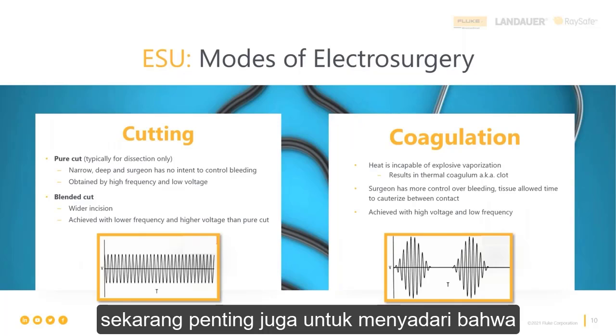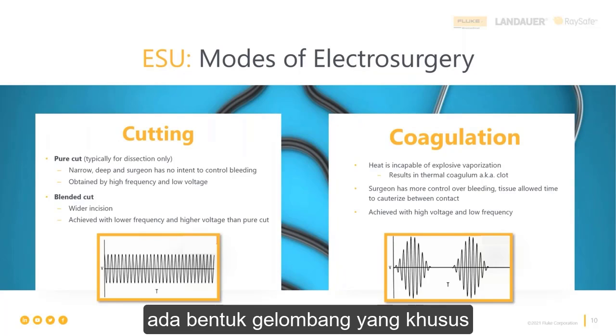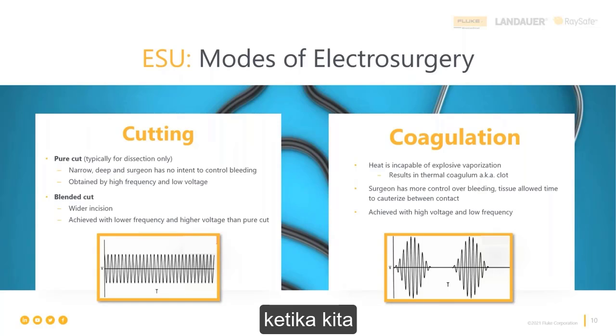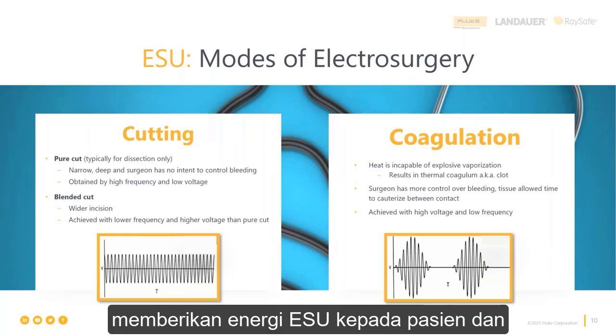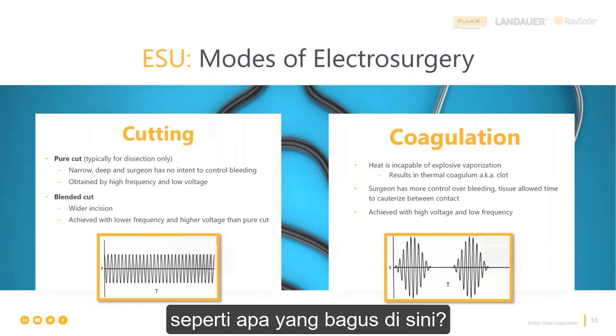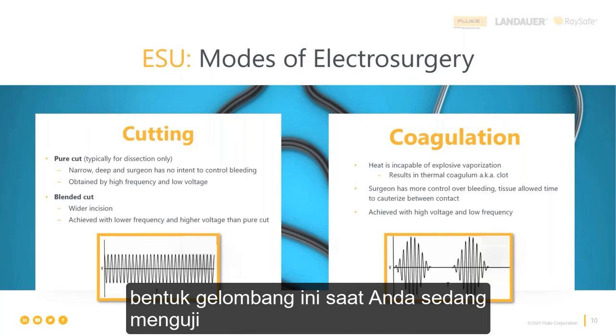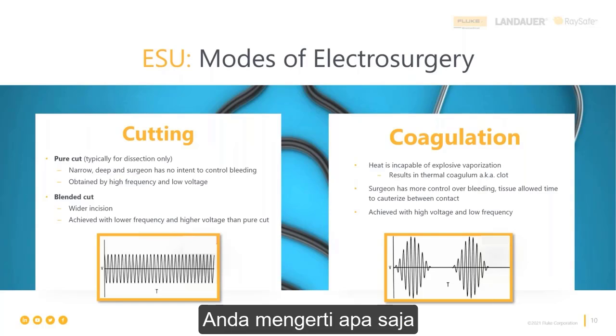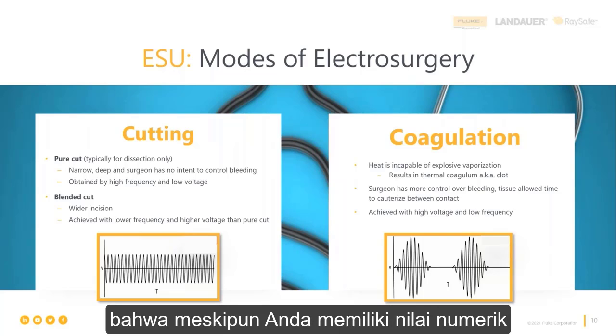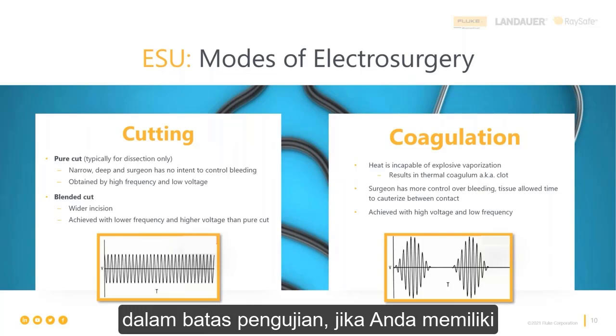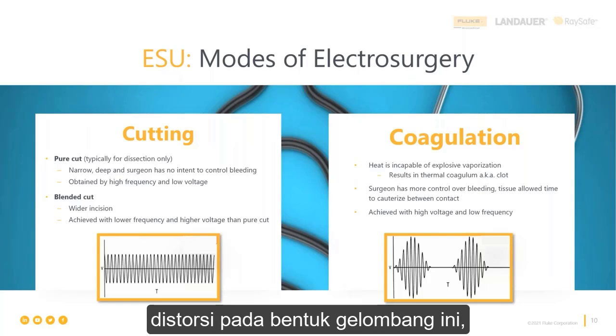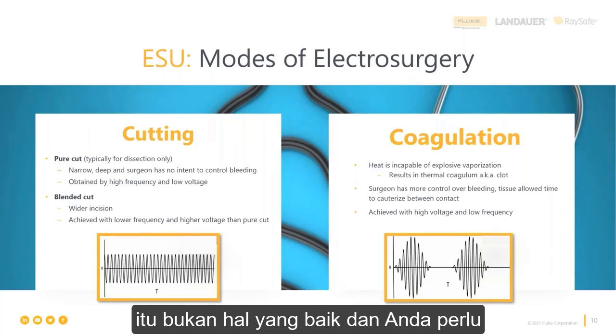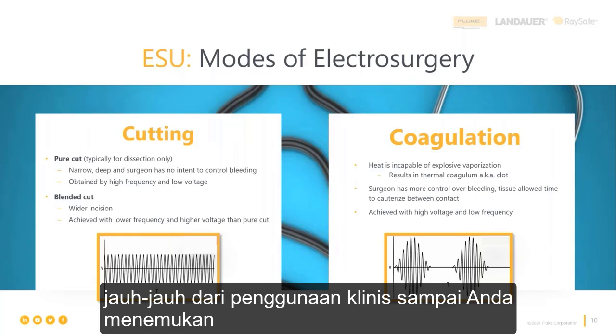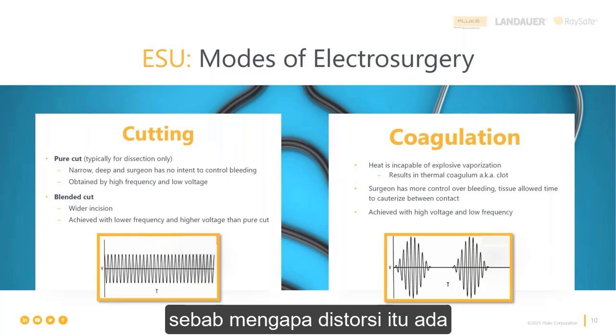Now, it's important to also realize that there are particular and very specific waveform shapes when we're delivering ESU energy to the patient. And these are important to understand what good looks like here, so that when you're viewing this waveform while you're testing, you can understand any differences. Even if you have numeric values that are within testing limits, if you have distortion on these waveforms, that's not a good thing, and you need to keep that ESU away from clinical use until you find out why the distortion is there.